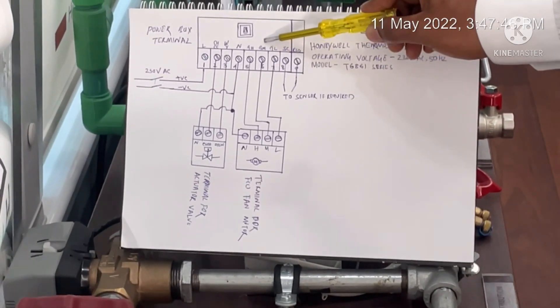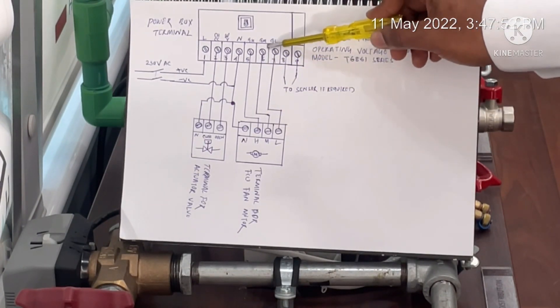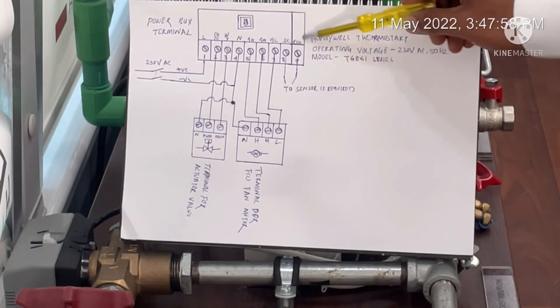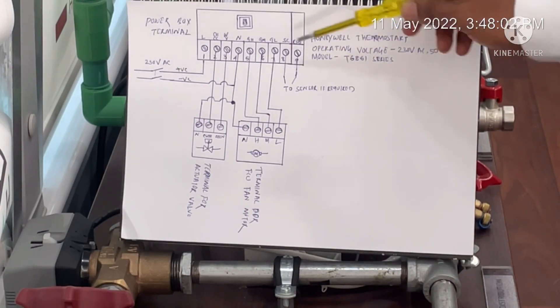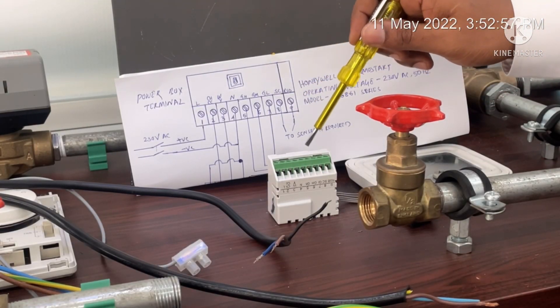The remaining terminals are: GH, which will be connected with the high speed cable; GM, which will be connected with the medium speed cable; GL, which will be connected with the low speed cable; and SC and RSP, both of which will be connected if we have an external sensor.